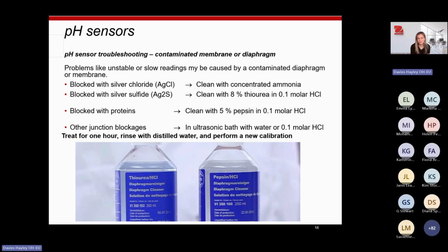If you've got samples that are high in proteins, then 5% pepsin works in 0.1 molar HCl. And if you've got something that's really sticking in the junction, and you can't clear the blockages of your junctions, what we suggest is popping your electrode in your electrode cleaning solution, whether it be the pepsin or the thiourea, into a beaker, and then put that beaker into an ultrasonic bath, and let the ultrasonic bath do its work, and that should agitate anything that's blocking the junction, and that should release that and hopefully get that clear.